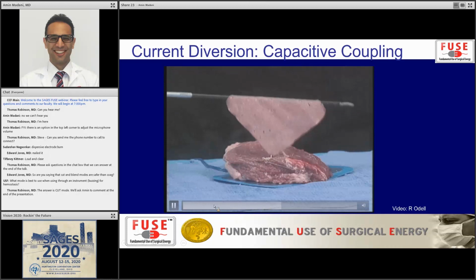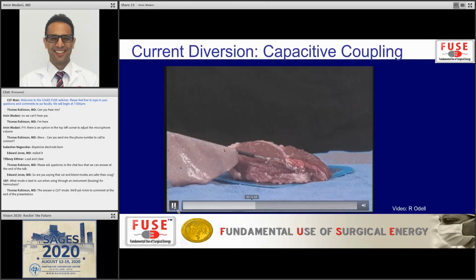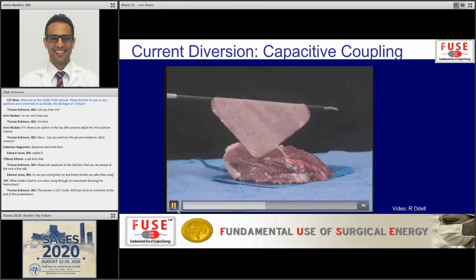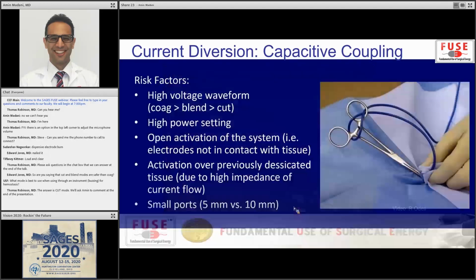And the key here, one of my pet peeves in the OR, is when people activate their instrument without touching the intended target. If I'm activating this in open air, the current has nowhere to go except through an alternative path. So make sure you're touching the target tissue, so that even if there's an alternative path, most of the current still goes where it's supposed to go. Never activate in open air.